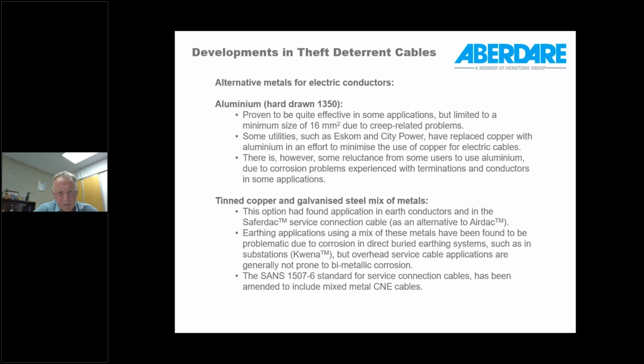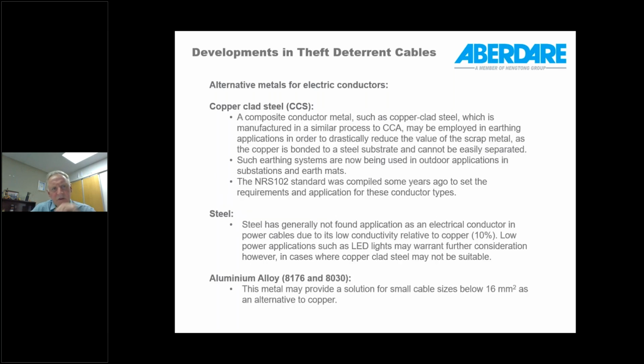The SANS 1507 Part 6 standard, which is service cables, has been amended to also include the mixed metal CNE service connection cables at this stage, although not the SNE version. Other alternative metals for electric conductors is copper-clad steel. We've seen quite a bit of this conductor being imported into South Africa. It's a composite conductor metal, and I'll explain a little bit further in the presentation.